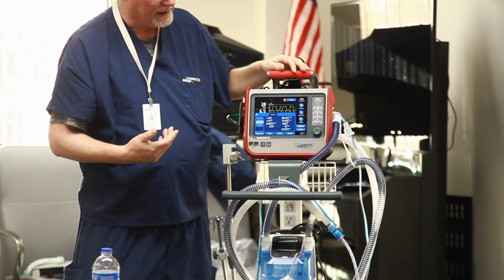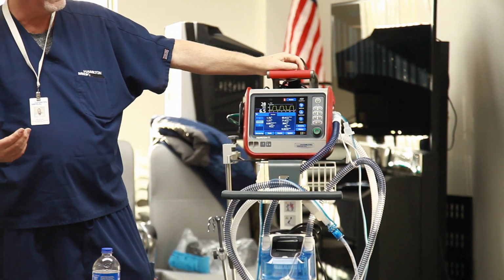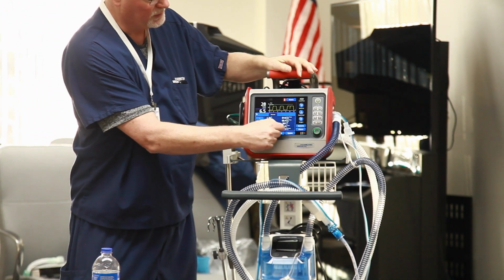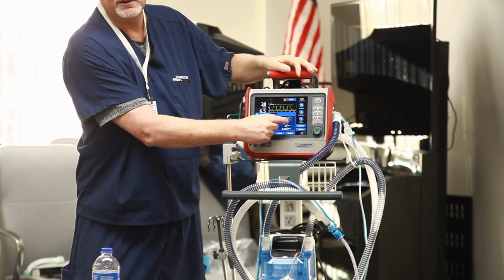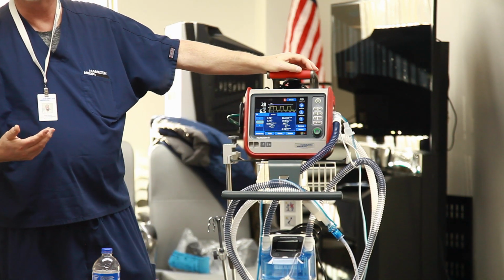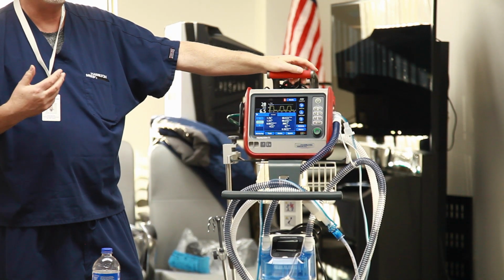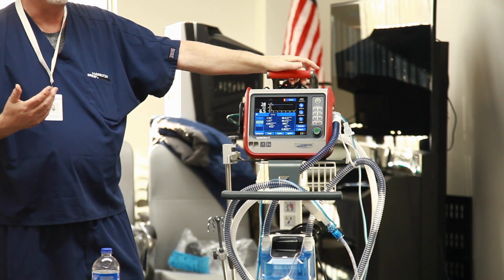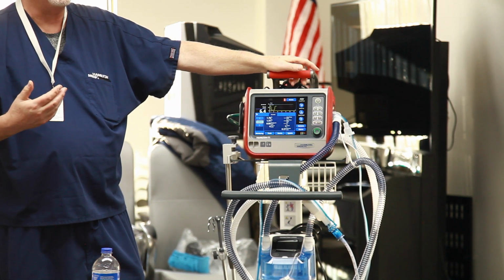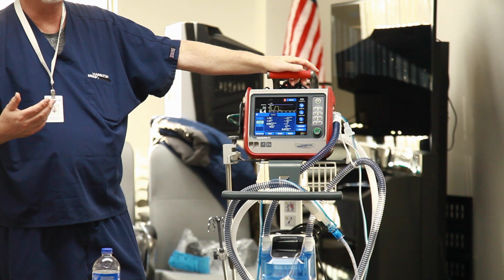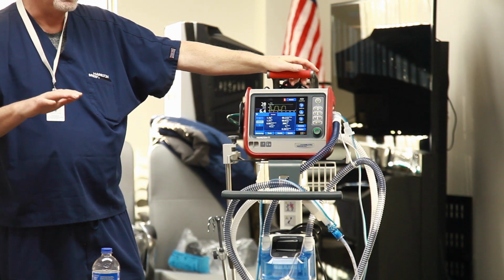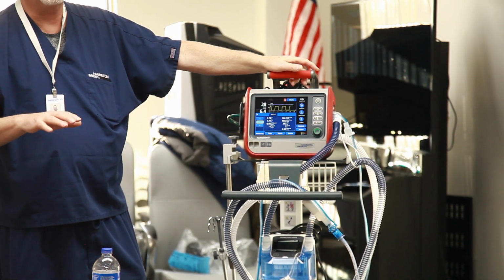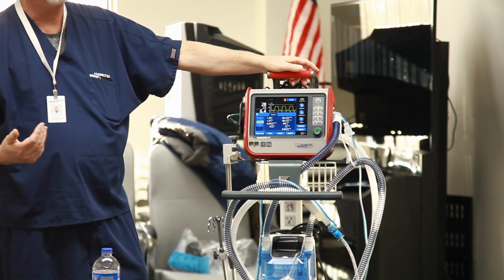Tab 2 is my non-invasive tab. I call it the non-invasive tab because it talks about my leak percentage and my liters per minute leak over here. That's what you want to look at if you put a mask on: what's my leak percentage? Try to tighten it up if it's at 50 or 60% or something like that if you can, but usually if it's at 30-40% or less, you're going to be fine.